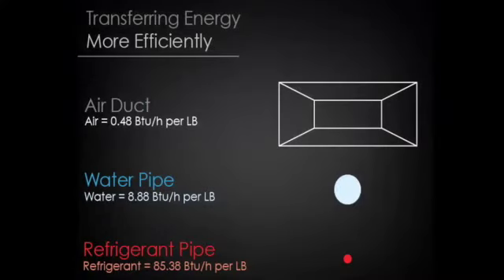Really, the main reason is because refrigerant is just so significantly more efficient at transferring energy than other modes such as air or water. This is getting a little bit into the enthalpy side of things, but air can transfer about a half BTU per pound of air at any given time. On the water side, you get almost 9 BTUs per pound of water, so you're considered about 20 times more efficient going from air to water. And when you go all the way down to refrigerant, as we show on the bottom, you can transfer 85 BTUs per pound of refrigerant. So you go 10 times more efficient than water once you go to refrigerant.